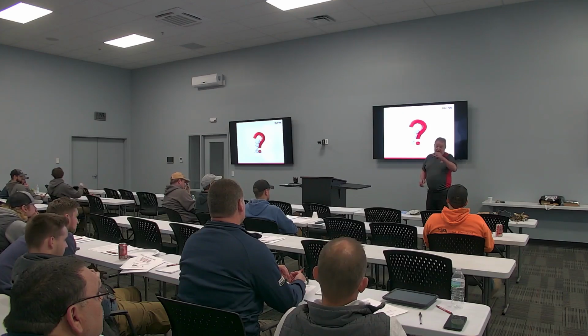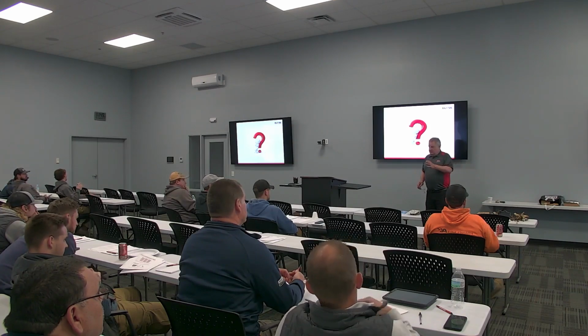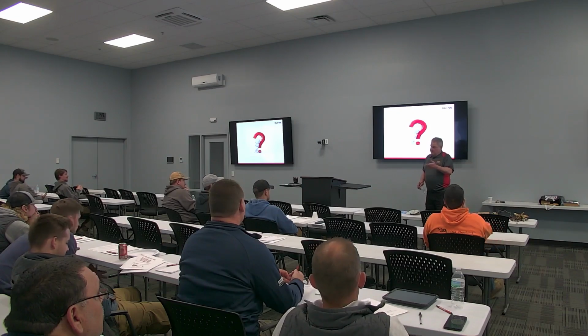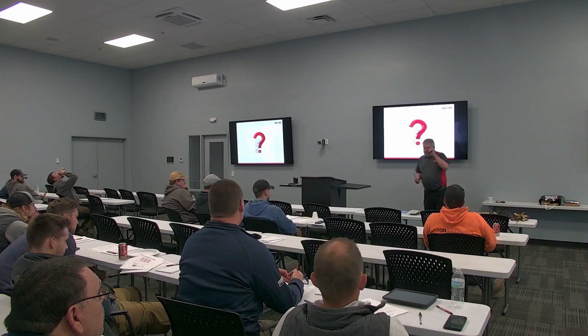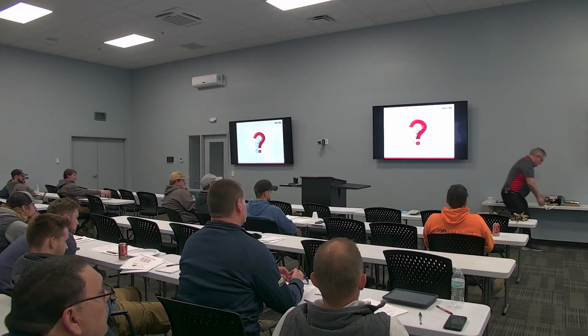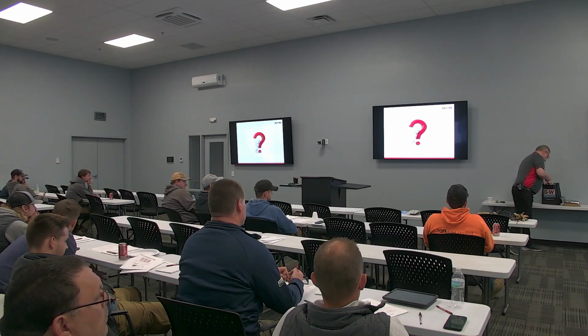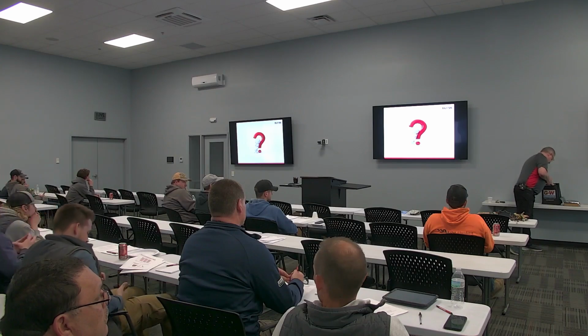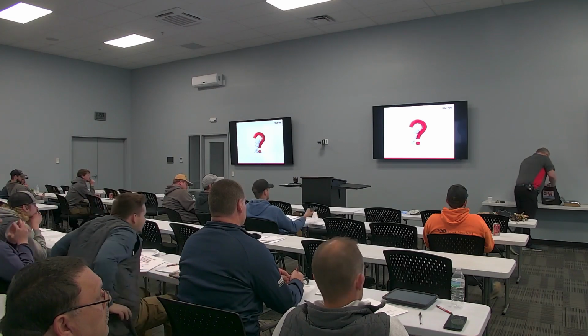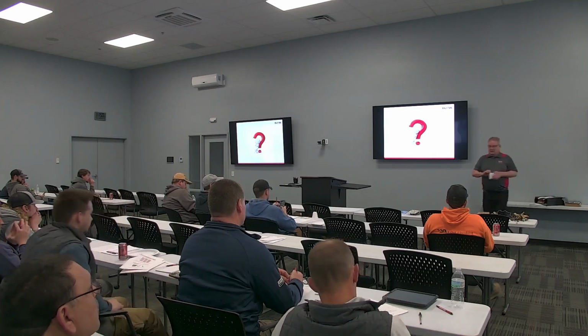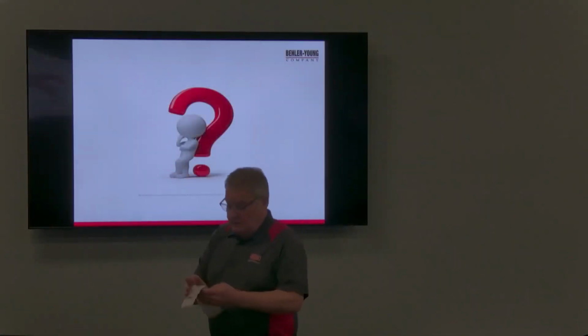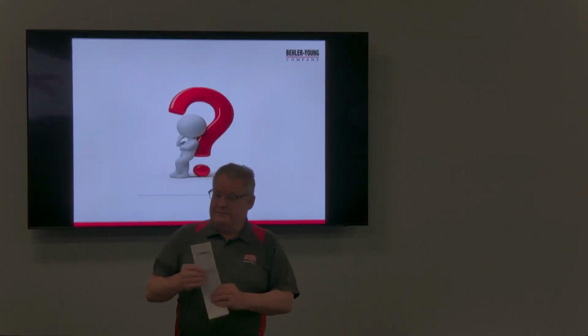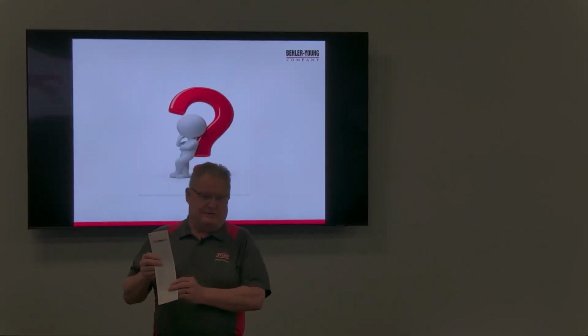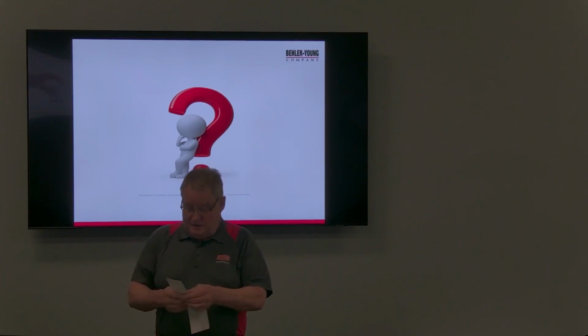Now, that being said, when Dave talked about superheat and subcooling, you use a PT chart. Now, your fancy gauges will do this for you, but a pressure temperature chart, I think I actually have one here. Maybe I don't. I do. So, PT chart. This is where your gauges get all those temperatures from. But this is all built into your gauges.